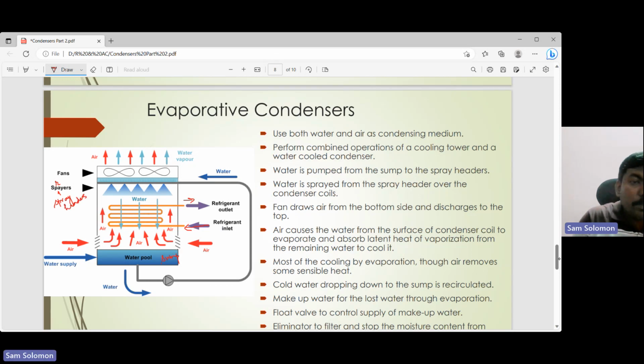This is the spray header, and this spray header has got nozzles over here. The opening is what we call the nozzle. So through the nozzle, water is going to be sprayed over the condenser coil. Okay, and as the water is sprayed over the condenser coil, the water is going to pass over this coil and remove heat from the condenser coil. As it moves over the condenser coil, the water evaporates by absorbing heat. And some of the water gets condensed, so water droplets can be seen on the condenser coil surface.